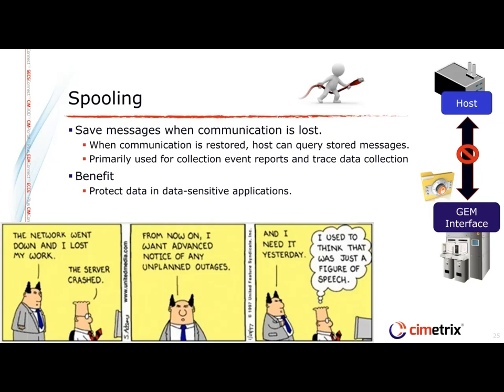GEM also has a feature called spooling, where messages normally sent from the equipment to the host can be saved automatically, so that if you lose communication, the GEM interface can save those messages. When you reconnect, the host system can ask for those messages again so you're not losing data.